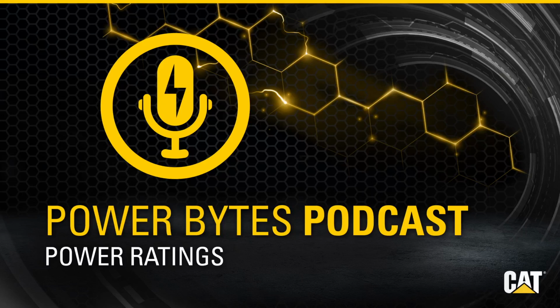The prime power applications also allow for unlimited hours of operation. But they also have one stipulation that allows for a 10% overload condition. So maybe you have a spike in load for a very short period of time. Typically, it's only going to allow for 1 hour in every 12 to have that 10% overload. An application you may see for these prime applications is something like an island, where during the day, you've got a lot of people using the power, so it's going to go up a little bit, but at night, it's going to go back down, and you just don't have a utility available, so the prime generator set would be the one that would operate to help support the island.